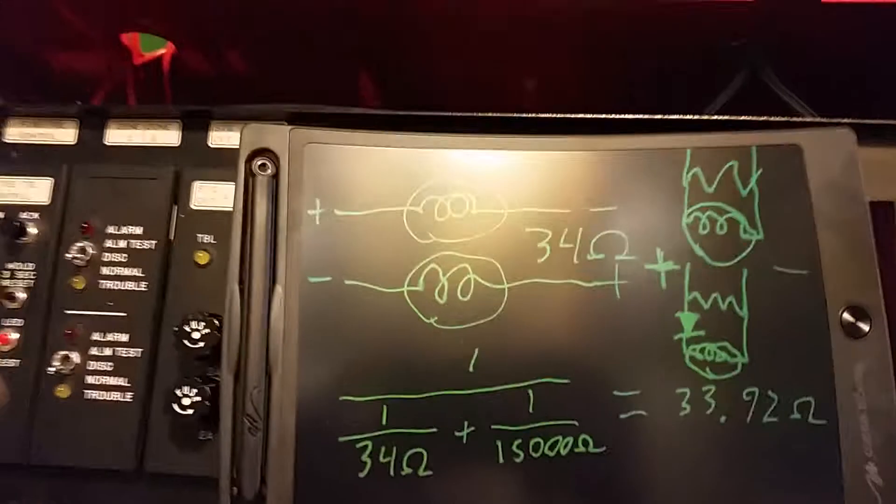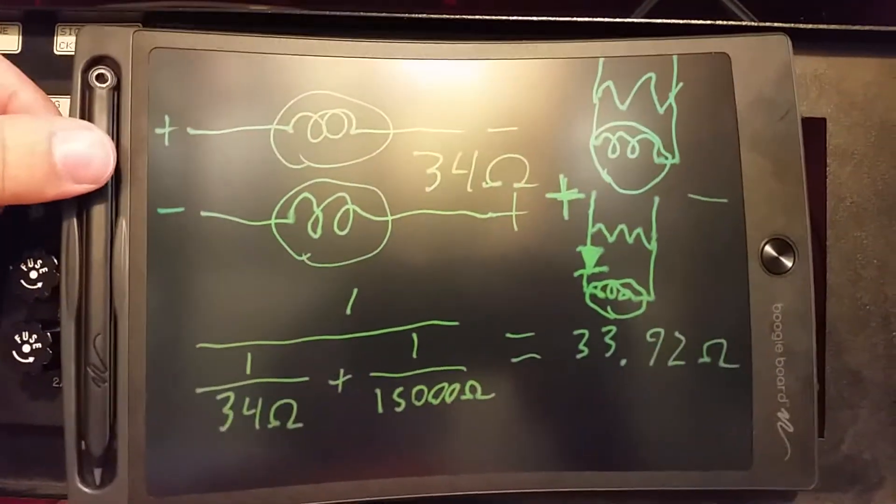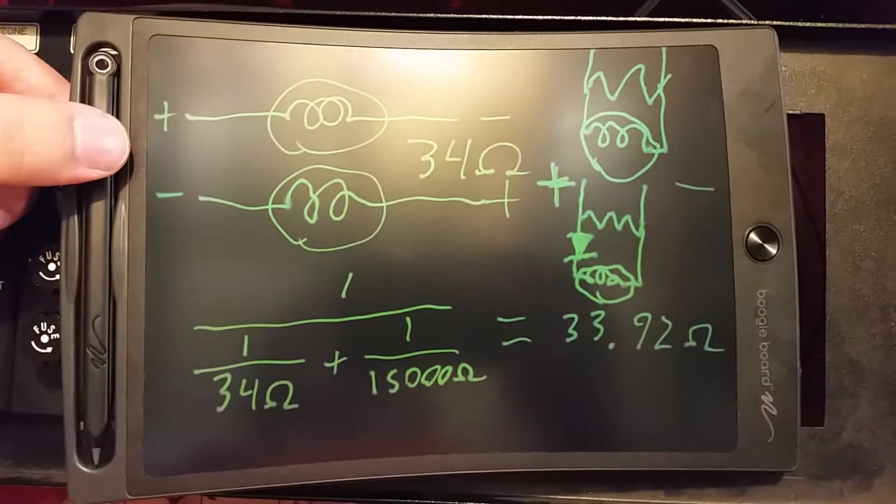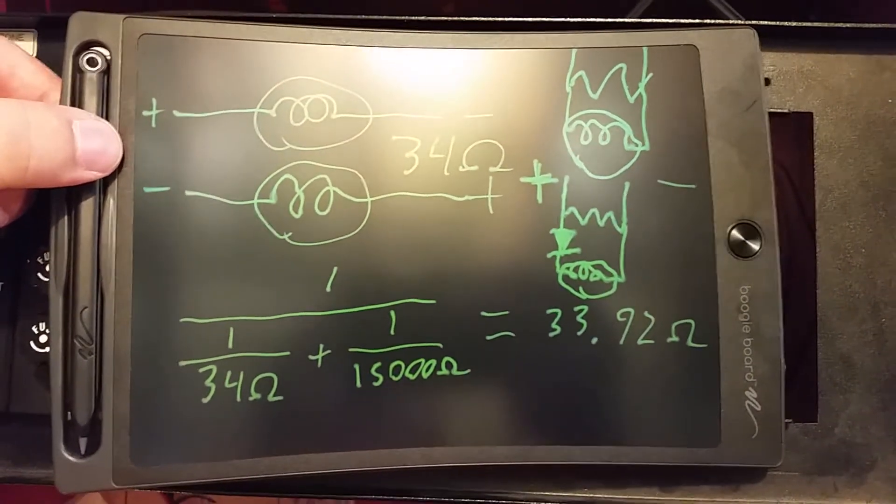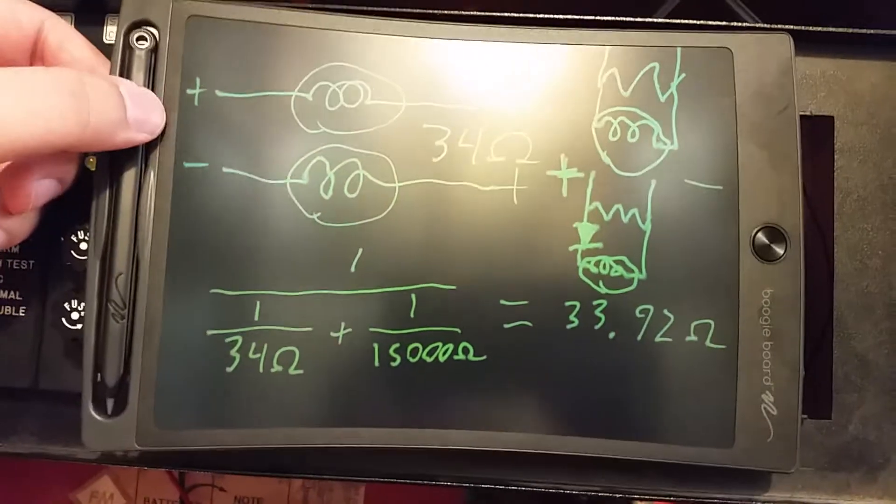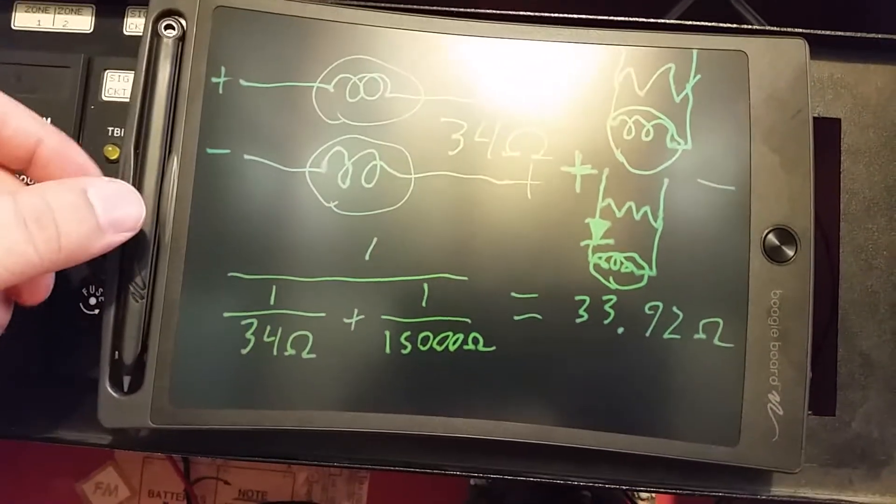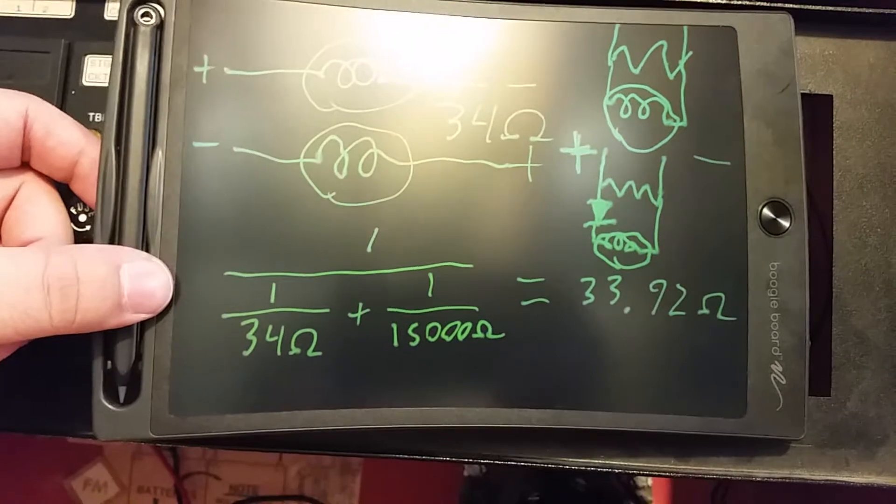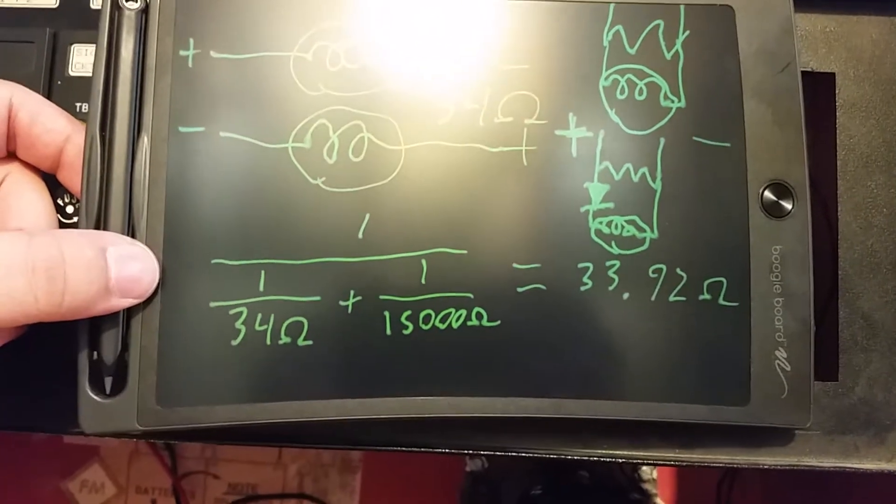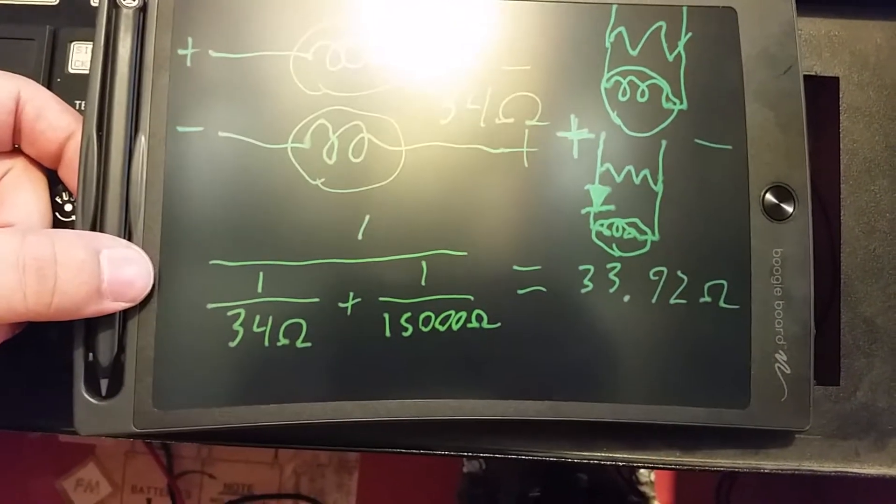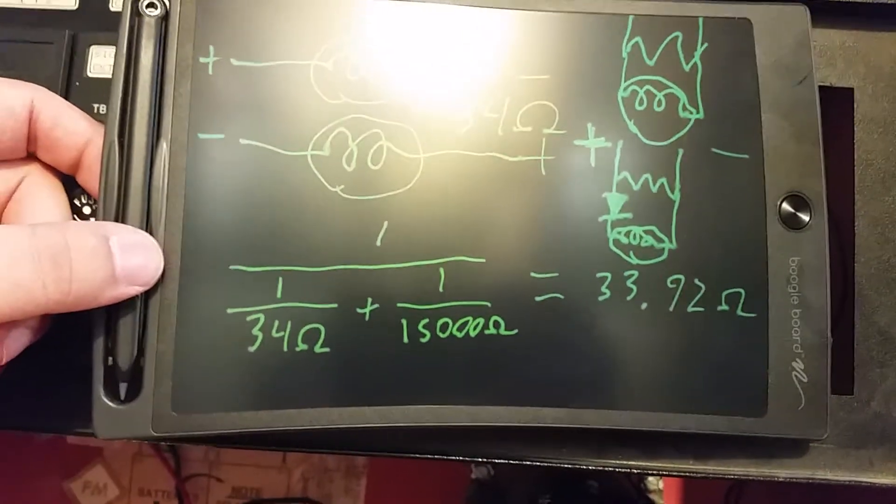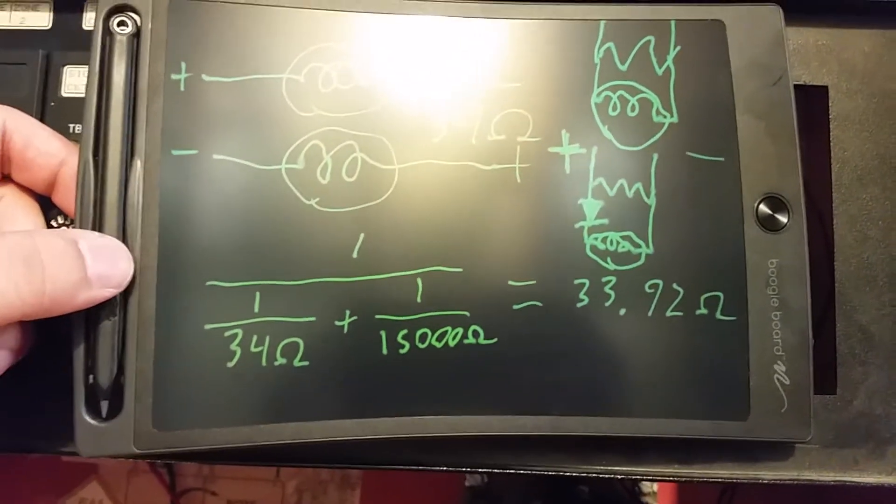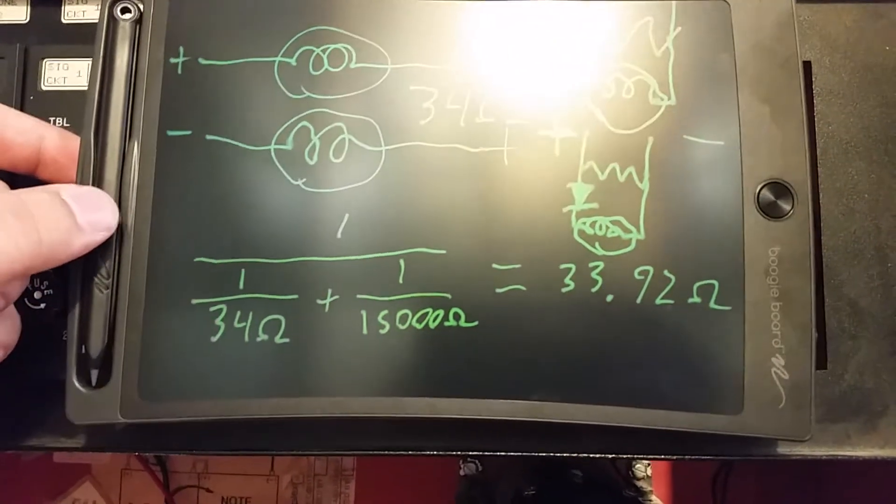The incandescent light bulbs, they kind of act as resistors, as shown right here. Current can flow in either direction. I measured the resistance of this light bulb. You get 34 ohms. A 15,000 ohm end-of-line resistor for the 2001. Combined in parallel with the 34 ohm light bulb, the panel will see that there is 33.92 ohms of resistance at the end of the circuit.